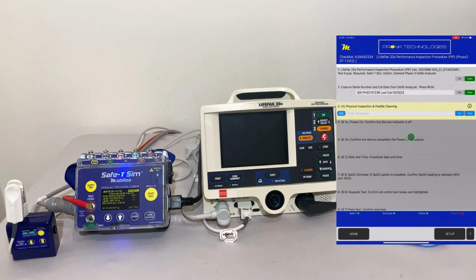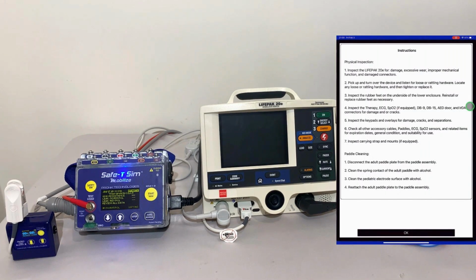As we mentioned earlier, we want to make sure that we do that physical inspection. It's listed here as the next step in our procedure. If you're an experienced technician, you may already know exactly what steps are required. But if you're a new technician, you may be unfamiliar or it may have been some time. If you want to recall exactly what needs to be done, you can tap on this little eye symbol, and it'll open up all of the exact steps from the service manual that we're required to do as part of this physical inspection. It lists all of the important things, and it's really important to follow this because defibrillators are high acuity devices, life support devices, and wear and tear devices. So we want to make sure we've done a great job of this physical inspection.